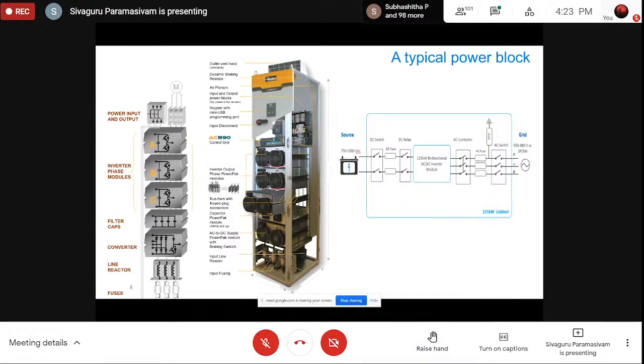So when DC is coming, or imagine that this is a wind power converter, when the power is coming from the generator, it needs to be protected with the fuses, and through the line reactor, it goes to the converter. The converter here is basically a frequency converter, because it also needs to get synchronized with the grid whenever there is a change in speed and torque in the wind turbine. And there are capacitor filters, then it goes to individual power blocks to ultimately connect back to the grid.